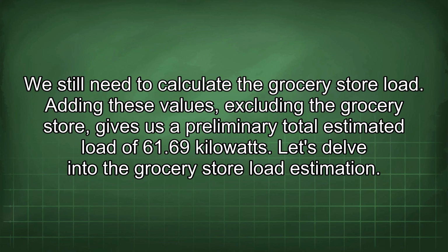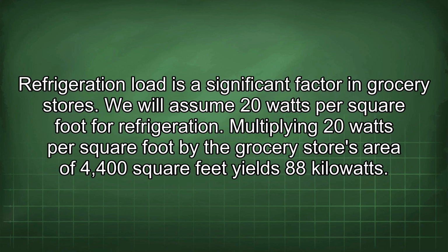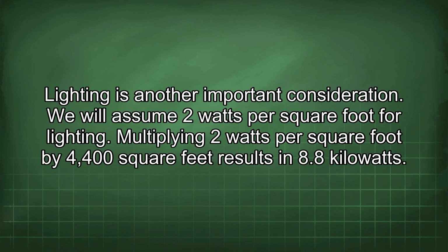Let's delve into the grocery store load estimation. Refrigeration load is a significant factor in grocery stores. We will assume 20 watts per square foot for refrigeration. Multiplying 20 watts per square foot by the grocery store's area of 4,400 square feet yields 88 kilowatts. Lighting is another important consideration. We will assume 2 watts per square foot for lighting. Multiplying 2 watts per square foot by 4,400 square feet results in 8.8 kilowatts.